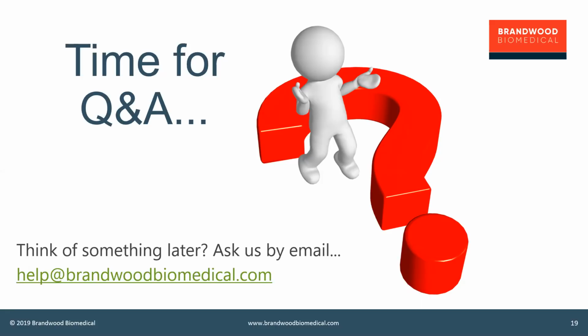If they don't, then you need to make sure that there's some validation of the documentation record system. Now, the biggest things here, and these are things I'll tell you from personal experience with notified body reviews and auditing recently, the biggest things that they're pushing in this space: cybersecurity, document retention, so the actual time that they're going to be retained, and disaster recovery.